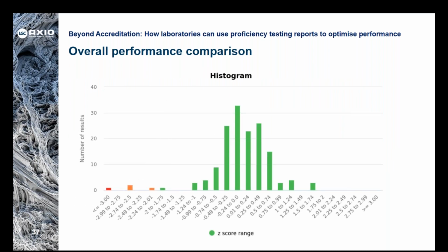The z-score range on the histogram that is available on the main report is helpful to see the overall performance of the analytes for the sample. This histogram indicates good performance for the majority of the participants by the nice distribution that is displayed. Labs that fell in the amber and red areas are likely to have a lab issue.